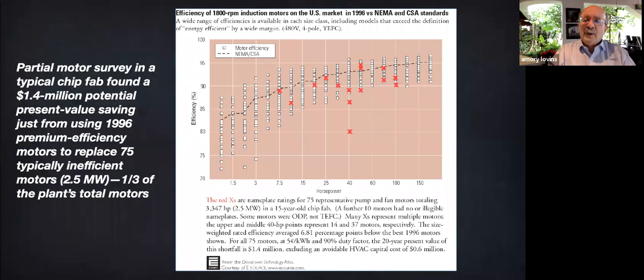First, we're often starting with a really juicy opportunity. Most motors in existing factories are unimpressive. An illustration of typical field findings, in this case for a third of the motors in a chip fab, typical of many kinds of factories a quarter century ago and even common today, found the nameplate ratings on the motors shown as red X's, where the white dots were all the motors on the market in 1996. Those above the dotted line are more or less at the now obsolete efficiency level called IE2. IE1 models were already no longer allowed to be sold, but you can see that's mostly what they had or worse. So this shows 2.5 megawatts of observed motors that could have saved $1.4 million net present value if replaced.